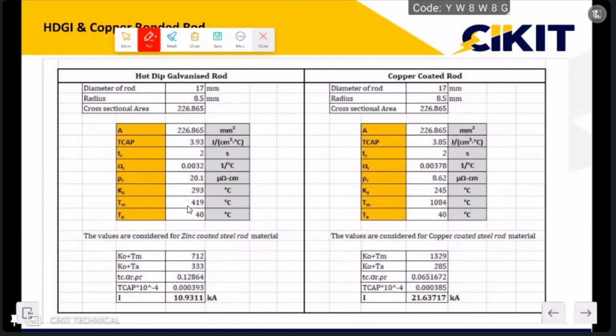So even though the core material is of the same dimension, like 17 mm in this case, depending upon the material which we are coating, the current carrying capacity will differ. Even though the difference is mainly because of 100 microns, the current carrying capacity is almost double for these copper coated rods. So we cannot simply say that the current carrying capacity depends only upon the cross section area, and that since the cross section area of the 17 mm dia HDGI rod and the 17 mm dia copper bonded rod are the same, the current carrying capacity also will be the same. We cannot say that, because the parameter which differentiates these two is the fusing temperature of copper and the fusing temperature of zinc.